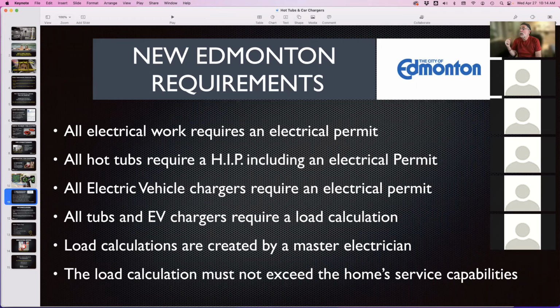Someone asks about the amp load added by an outdoor hot tub. It depends, but a normal standard hot tub is anywhere from 30 to 40 amp draw on a 50 to 60 amp rated hot tub, because we only go to 80%. That 30 to 40 amps is what's used on the load calculation to determine if you're exceeding your electrical service coming into the house.